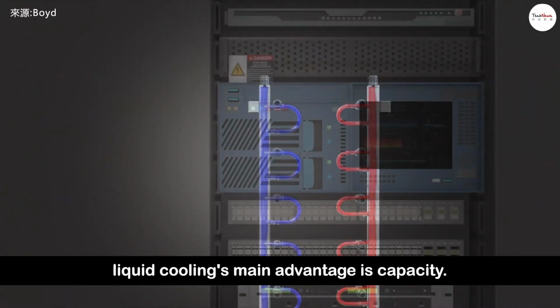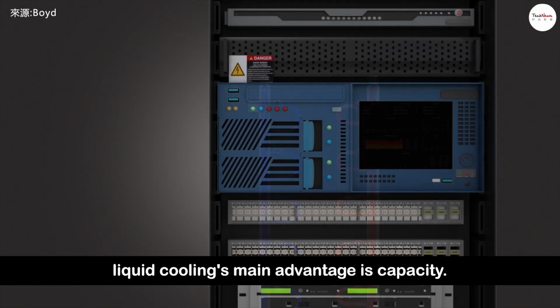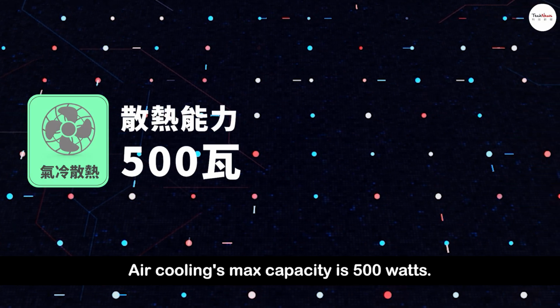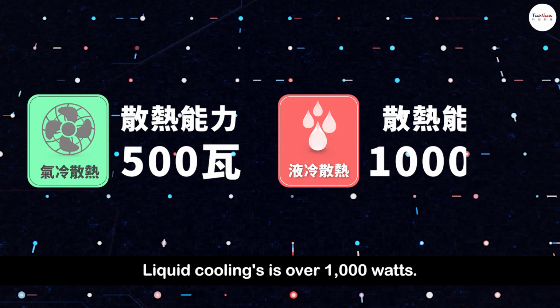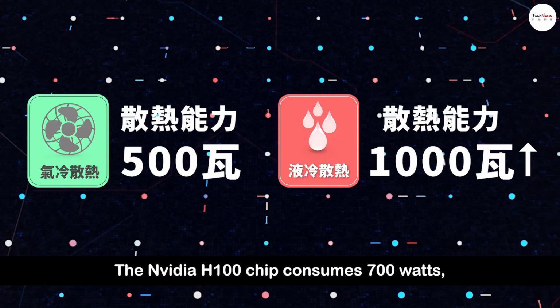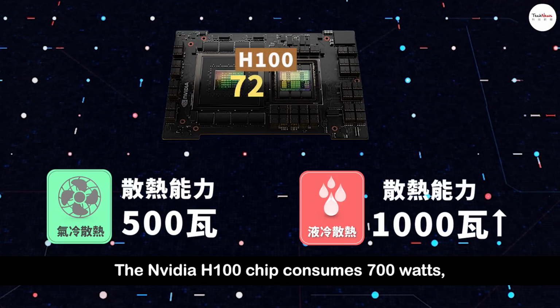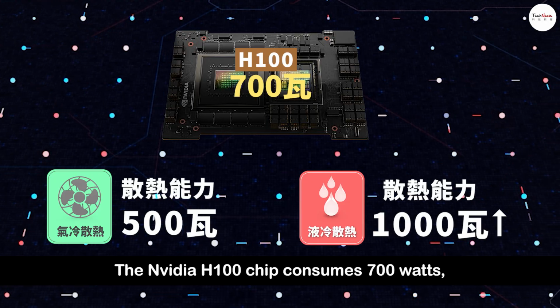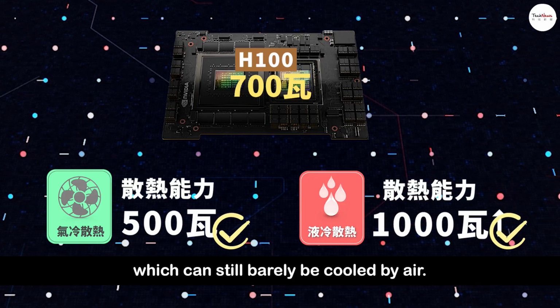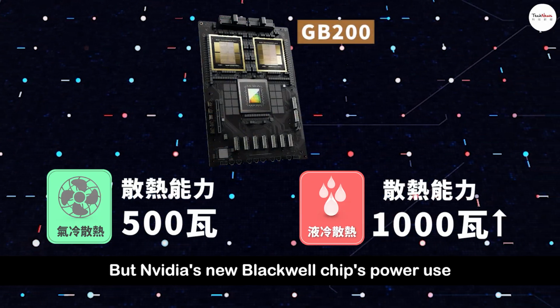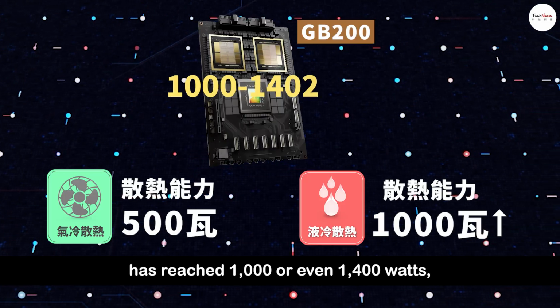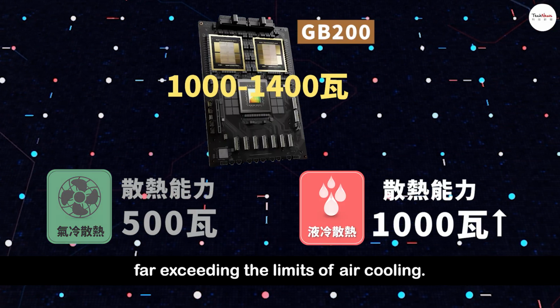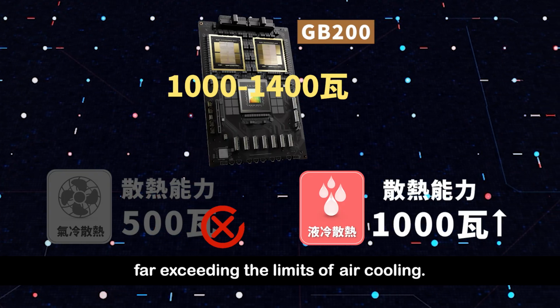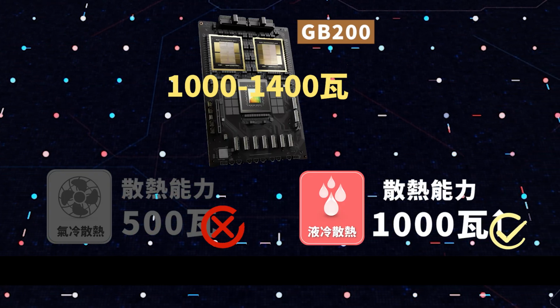Compared to air cooling, liquid cooling's main advantage is capacity. Air cooling's max capacity is 500 watts, while liquid cooling's is over 1,000 watts. The Nvidia H100 chip consumes 700 watts, which can still barely be cooled by air. But Nvidia's new Blackwell chip's power use has reached 1,000 or even 1,400 watts, far exceeding the limits of air cooling. Liquid cooling becomes the best choice.